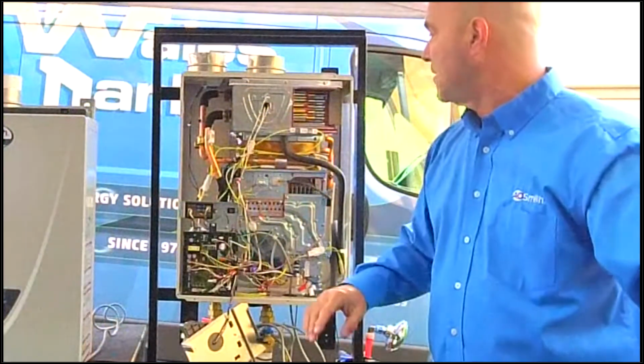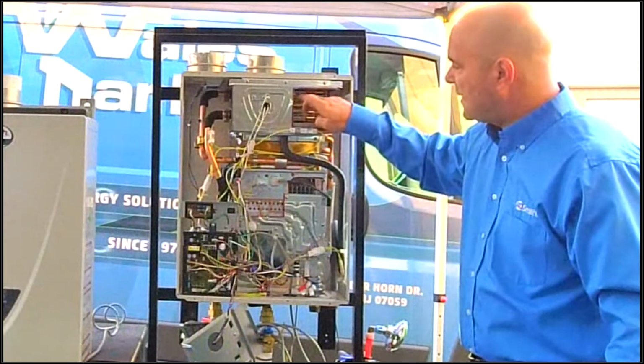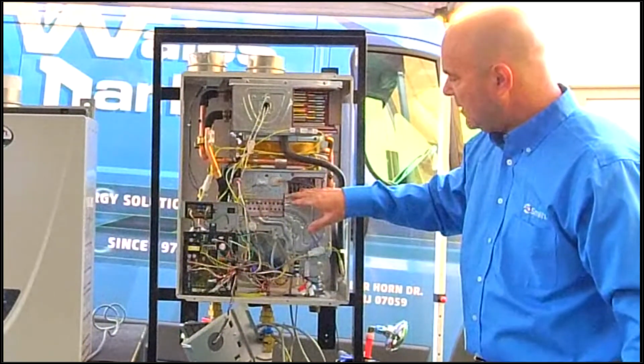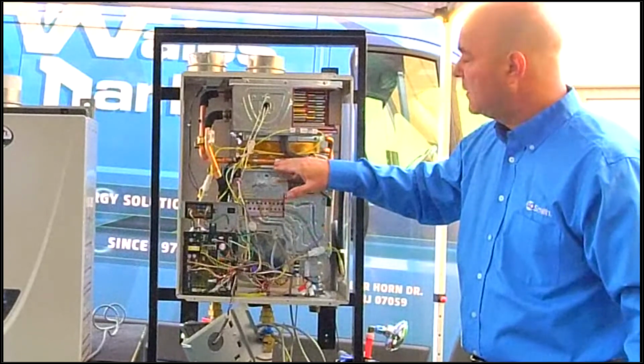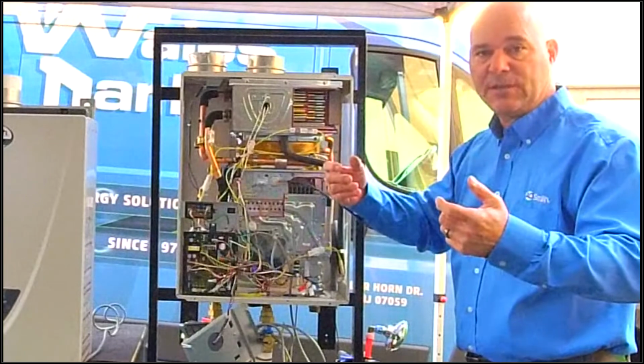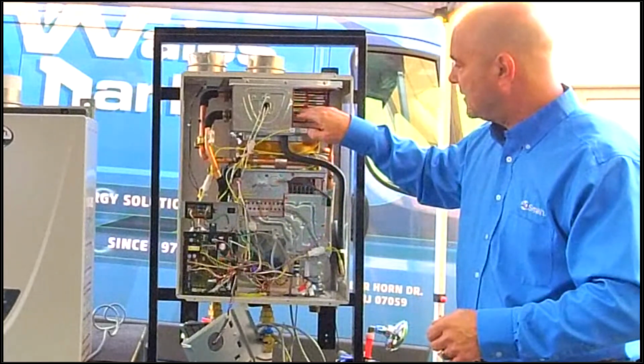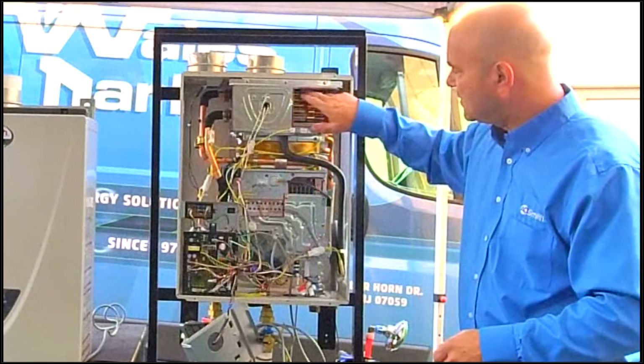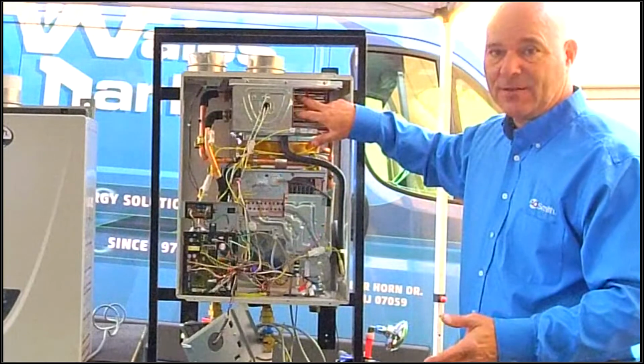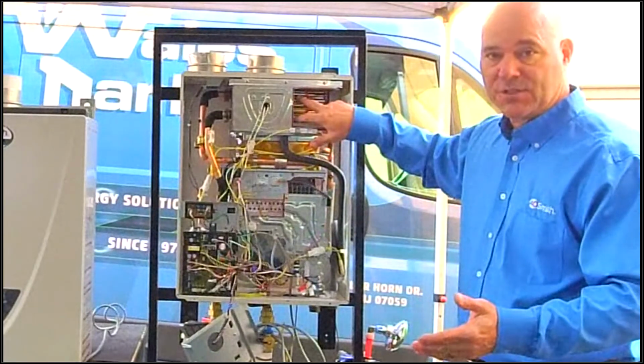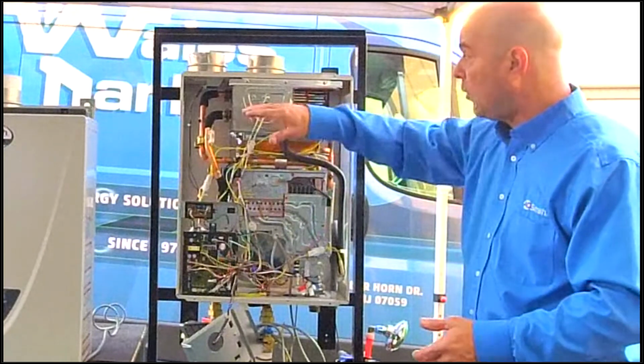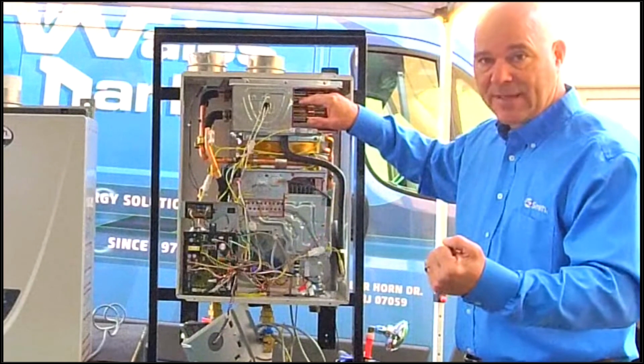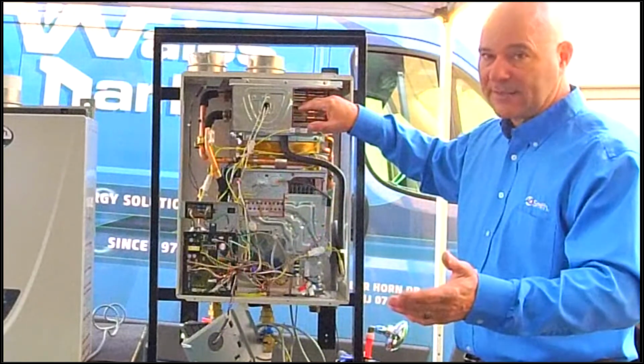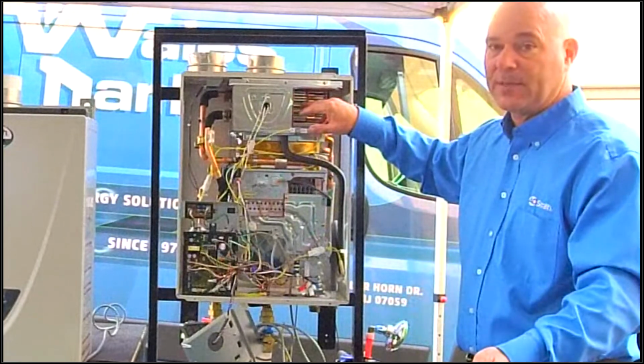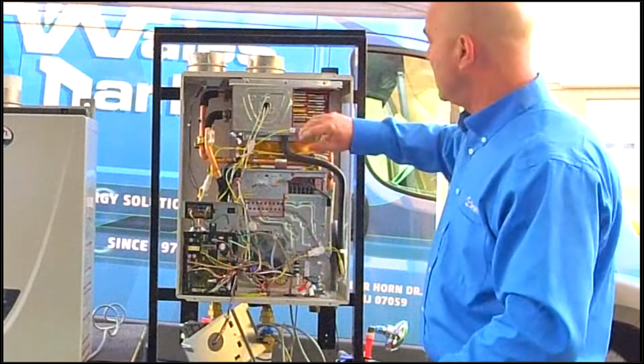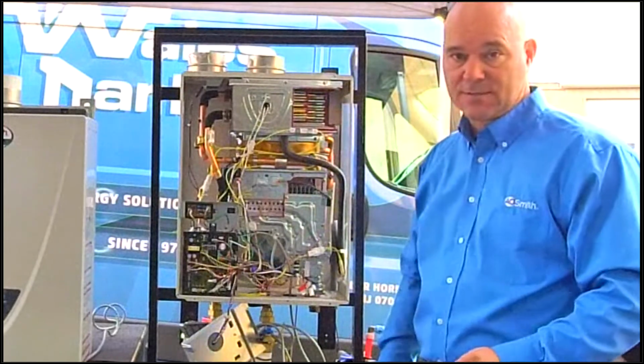So in that secondary heat exchanger location, our flue gases are passing by the outside. So combustion happens here. It goes over the primary heat exchanger first. We extract about 60% of the energy out of the flue gases. It transfers into the secondary heat exchanger. The flue gases pass this stainless steel heat exchanger. This is 316L stainless steel because this is where all the condensing should take place. We'll go by this, the coldest water quenches and cools down that flue gas. We create condensation. Every gallon of condensation, you're saving 8,080 BTU, keeping it in the home. And the flue gases, after they pass over this heat exchanger, will exit out through the exhaust.